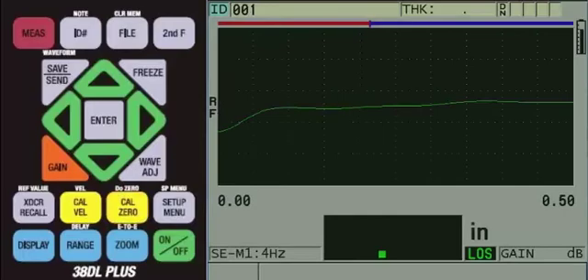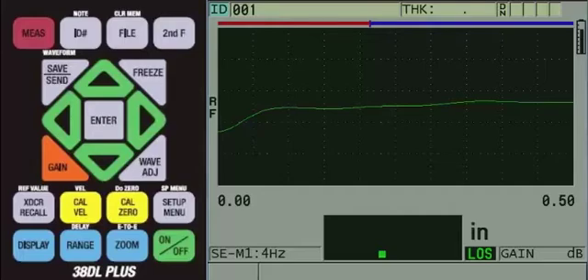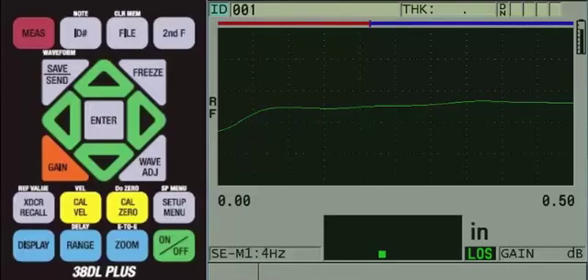The default setup we recalled has a default sound velocity for fiberglass, since this transducer is most commonly used to measure thick composites. Therefore, we do not need to change the default sound velocity. We will, however, need to change our range.